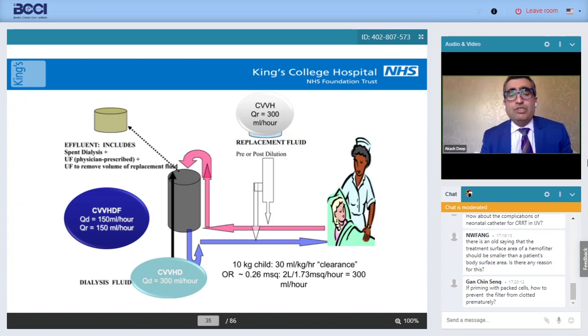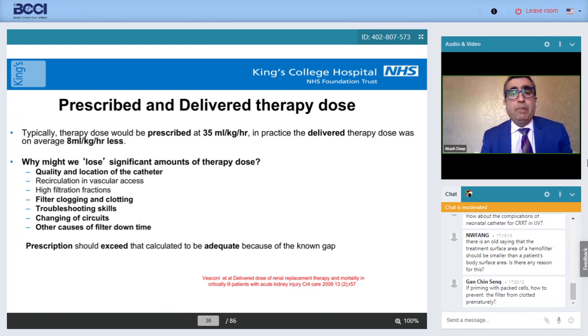This is a 10 kilo child, and if you're giving a dose of 30 mils per kilo per hour, or 2 liters per 1.73 meters square per hour, you're giving 300 mils. If it's pure hemofiltration, this is your dose. If it's pure dialysis, again, the dose remains the same, but everything is going as diffusion. And if you have a CVVHDF, you are splitting it 50-50. So dialysis is 150 and replacement fluid is 150.